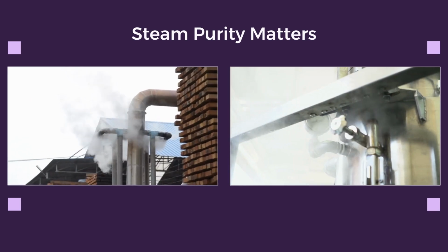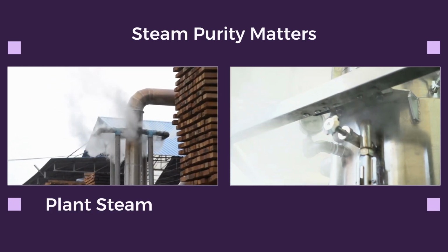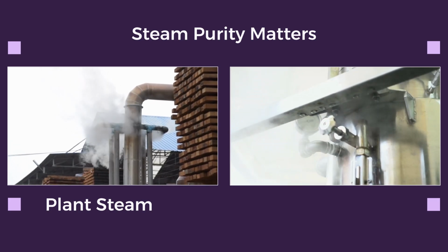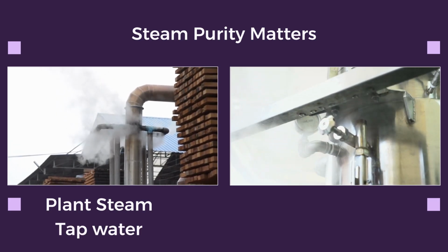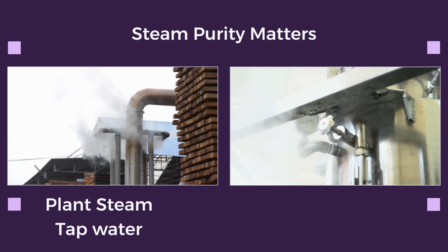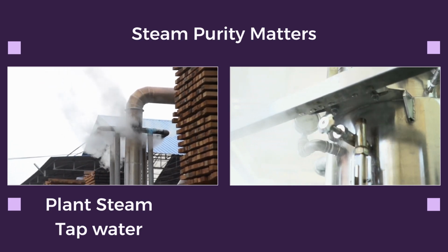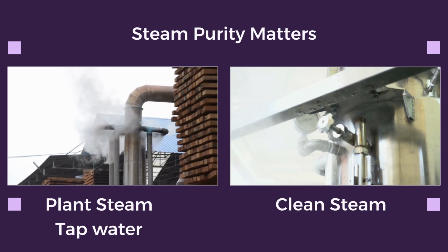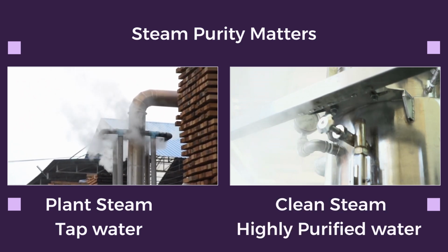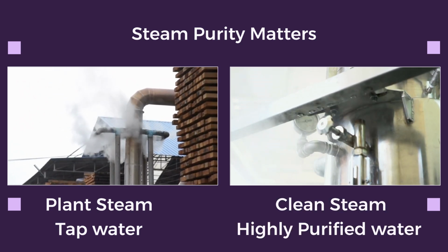First, purity. The steam in your building's heating pipes is plant steam. It's made from tap water and often contains additives to prevent corrosion. You never want it touching a sterile product. For pharma and biotech, we use clean steam, generated from highly purified water in specialized sanitary equipment.